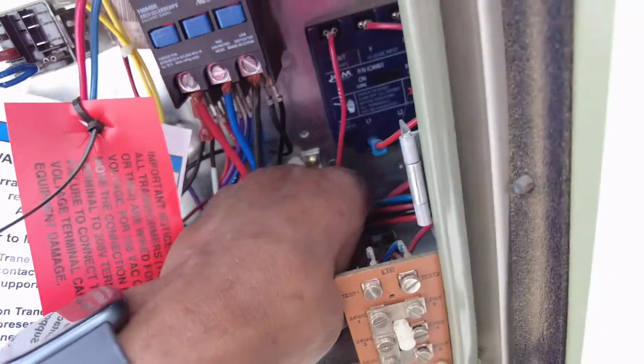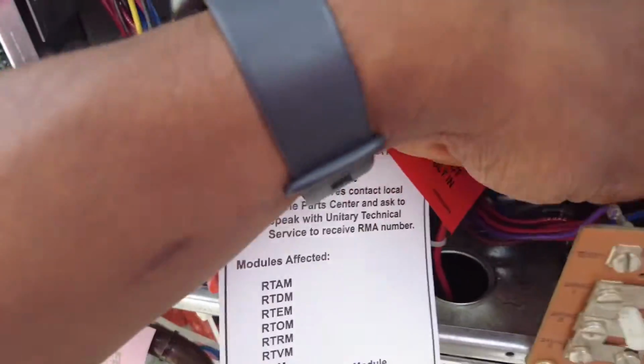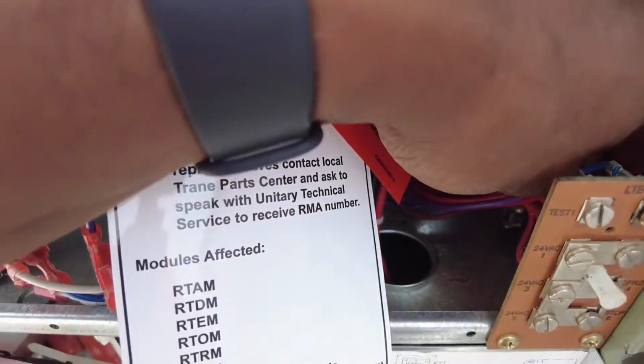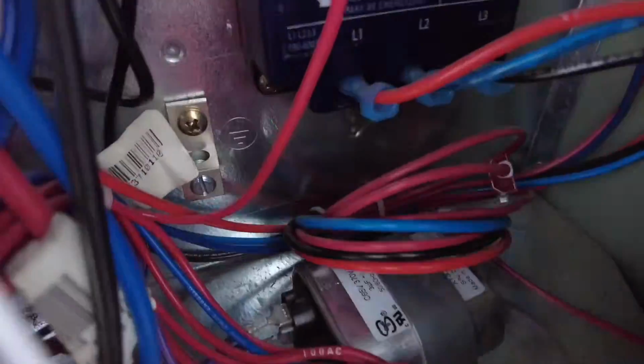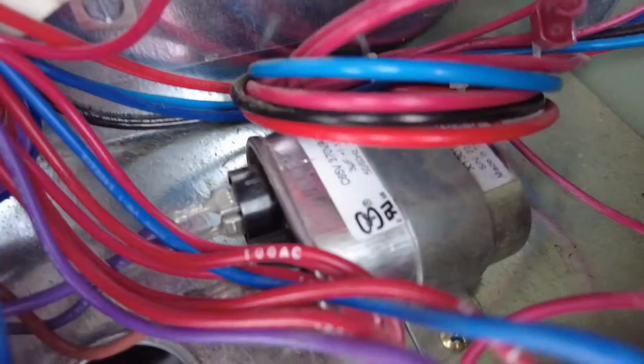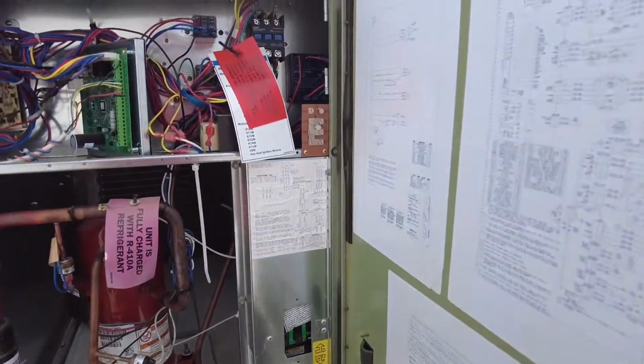So that's the 3.5. Now let me make sure that that's the real rating on that thing. Okay, I went ahead and slid it forward, and as you can see, sure enough, that is a 3 microfarad capacitor for that condenser fan motor.